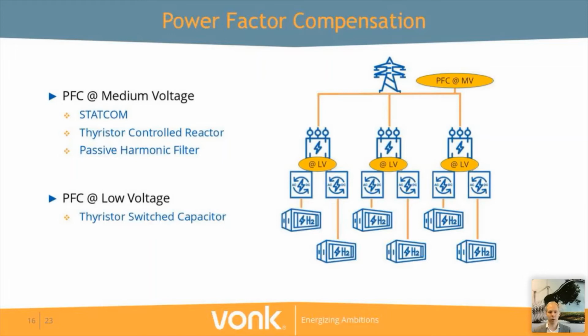The first one is called STATCOM. That's an IGBT-based system with full dynamic compensation, and it has two main advantages. The first one is that it covers both power factor compensation as well as harmonics. So it works on both levels of compliance. The second advantage is that compared to a thyristor controlled reactor, which I will describe next, it takes less floor space.